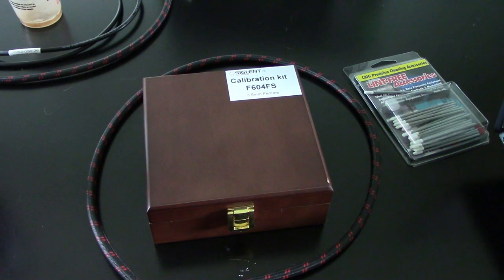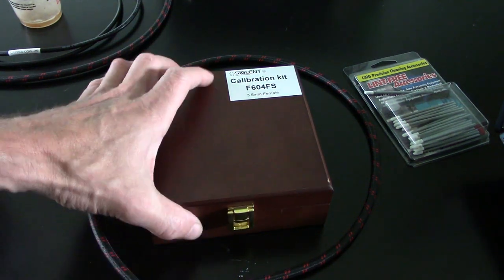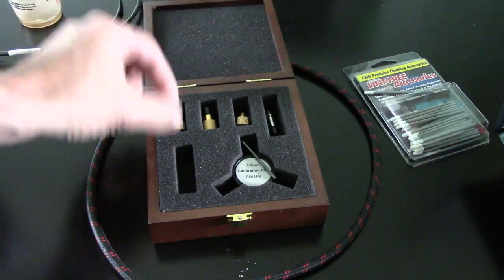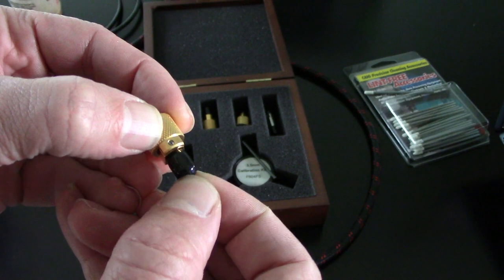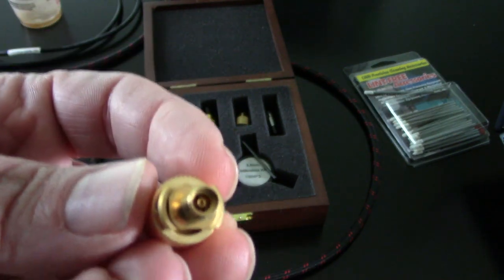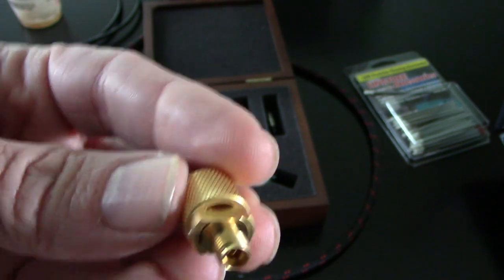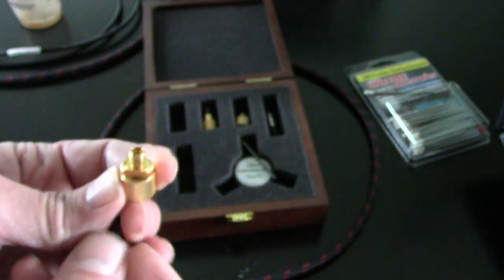Here we've got a Siglent F604FS female calibration kit. This is a three and a half millimeter. Each of the short, open, and load elements have a cap. We want to remove that rubber element and you can see with the three and a half millimeter there's air as the dielectric between the center conductor and the outer. We've got some gold plating or metalized plating to help longevity.